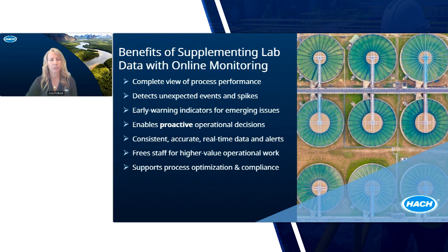Online monitoring gives us visibility during the hours when lab work isn't happening, between shifts, overnight, weekends, or even upcoming holidays. It provides real peace of mind about what's happening in the process. Online analyzers also reduce chemical exposure. Instead of driving samples across the plant or handling reagents repeatedly, the analyzer does the work automatically and safely at the point of measurement.